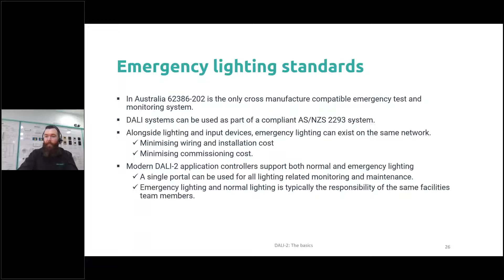The other advantage of using a DALI 2-based system is that a lot of modern DALI 2 application controllers can support both normal and emergency lighting on the same system, often on the same network. For facilities management teams looking after these buildings, it gives them a bit of a one-stop shop to manage all areas of their lighting control.